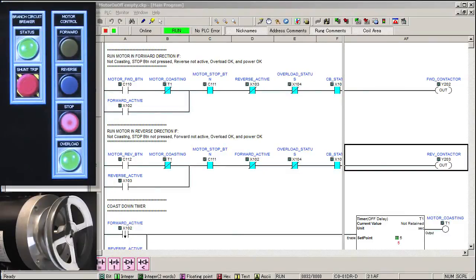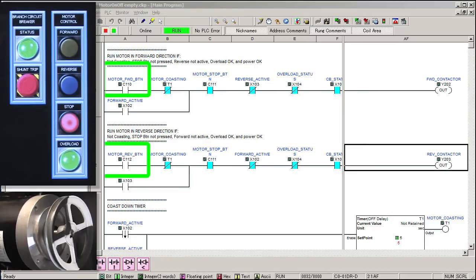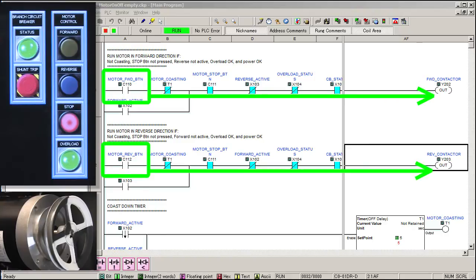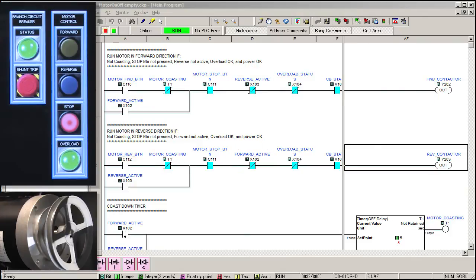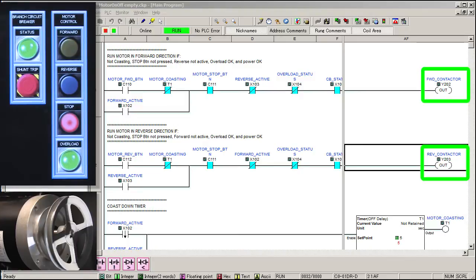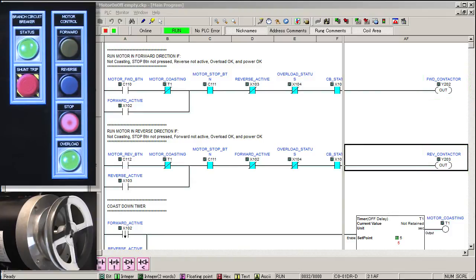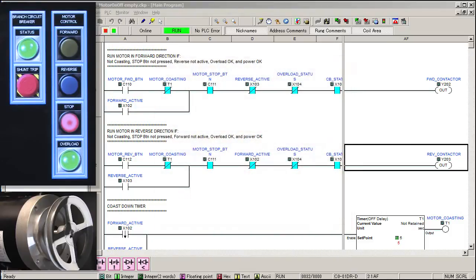This all looks great, but there is a potential problem. What happens if the user presses both the forward and reverse buttons at exactly the same time or even just real close at the same time? Well, the power will flow through all these contacts on both the forward and reverse rungs because their respective AUX contacts won't have closed yet. It can take an AUX contact 10 or 20 milliseconds to close, which means we won't see that feedback until many scans later. Which means both of these outputs will fire, which will engage both contactors, which will short out the power mains. And that's a bad thing, right? Well, not really, because it physically can't happen in this system. Remember, in the hardware video we installed a mechanical interlock to prevent just this scenario. It physically won't allow two contactors to engage at the same time. Because of that, one of the AUX contacts can't close so that circuit will never seal or latch.